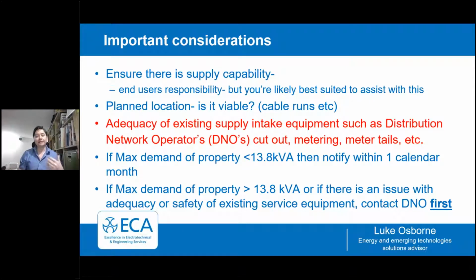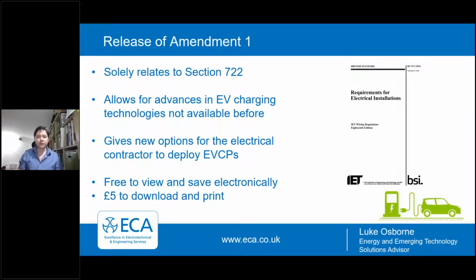If the maximum demand of the property is greater than that, or, as I mentioned, if there's an issue with the adequacy of the existing service equipment, you must contact the DNO first for approval. Because if the demand is so great and it's going to push over what they expect to be drawn from the property, they may need to check that the connections to the network are strong enough to make those connections. So on to Amendment 1. Okay, this is just over a year ago that this came out, and Amendment 1 to the wiring regulations solely relates to Section 722. It allowed for advances in EV charging technologies which hadn't been available before, and it also gives new options for the electrical contractor in how to install electric vehicle charge points.